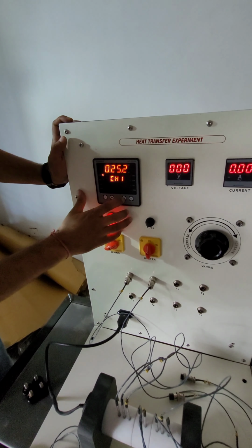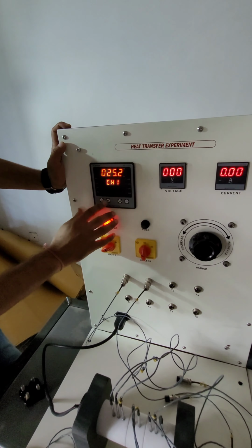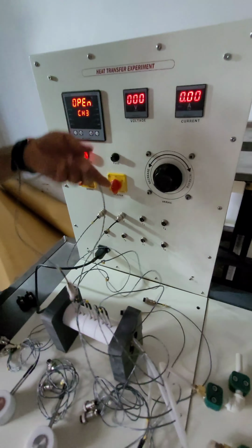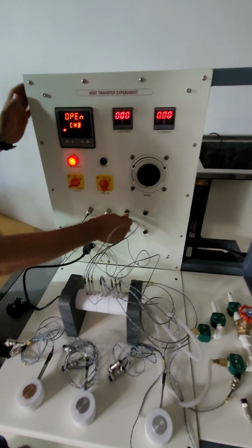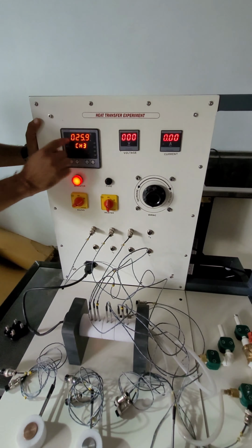with the help of these scrolling buttons, you can scroll between the different channels. This is channel number 2. It also starts showing. When it goes to channel number 3, this will show as open because nothing is connected here. So I can connect temperature sensor number 3 also.